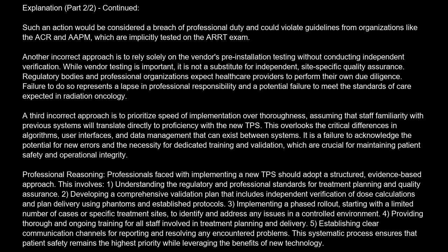Professional reasoning. Professionals faced with implementing a new TPS should adopt a structured, evidence-based approach. This involves 1. Understanding the regulatory and professional standards for treatment planning and quality assurance. 2. Developing a comprehensive validation plan that includes independent verification of dose calculations and plan delivery using phantoms and established protocols. 3. Implementing a phased rollout, starting with a limited number of cases or specific treatment sites, to identify and address any issues in a controlled environment.